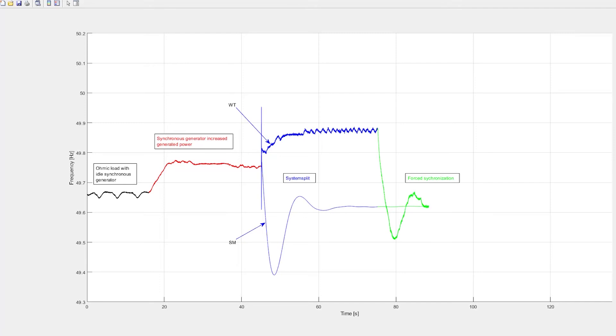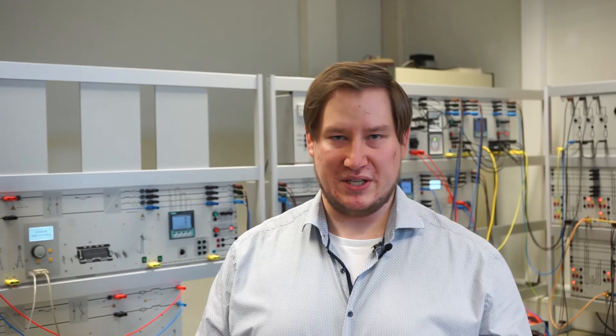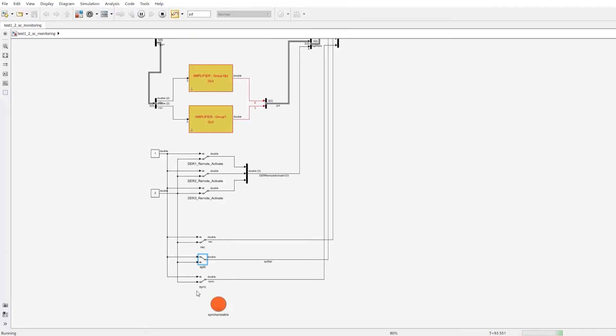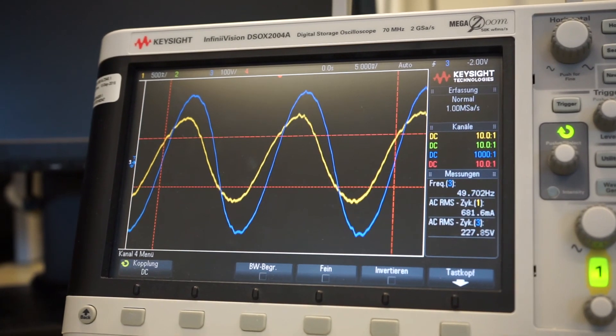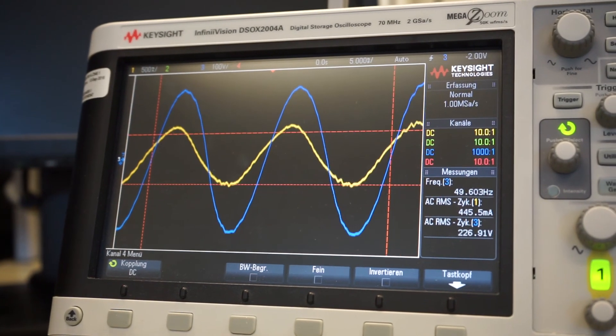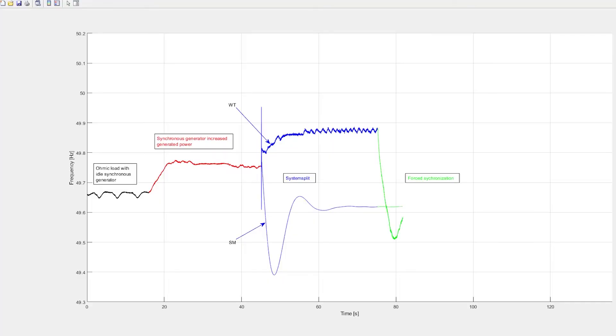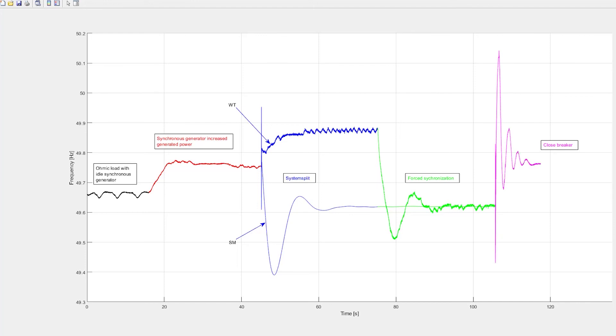To connect both grids again, we have to synchronize them. Since we can control our wind turbine in a more general way than the synchronous machine, we will force it to achieve the same frequency and an acceptable angle between the two grids. Let's force the wind turbine to synchronize with the simulated synchronous machine. We are now able to connect the grids. Since we were forcing the wind turbine to reach the simulated synchronous machine's grid frequency, its designated operation point on its droop curve will result in a clearing process. Both primary controls will achieve an equilibrium so that the pre-split frequency is achieved again.